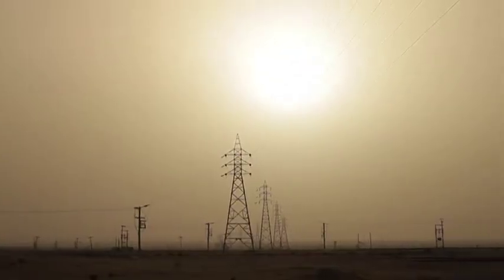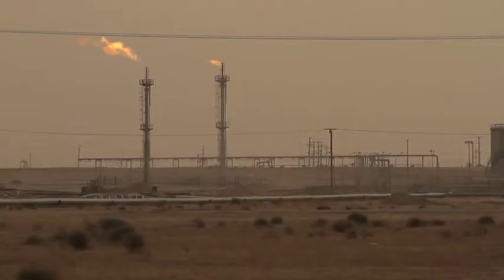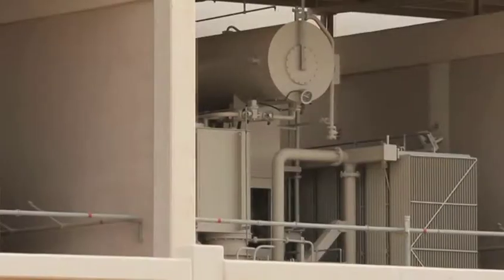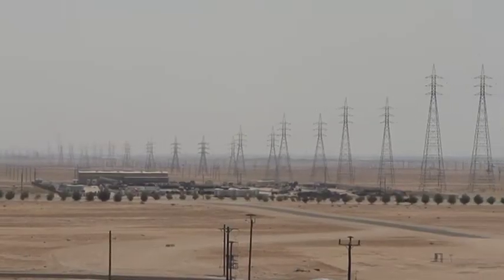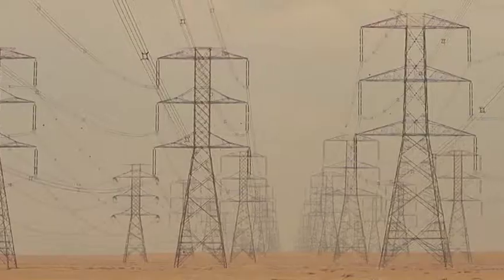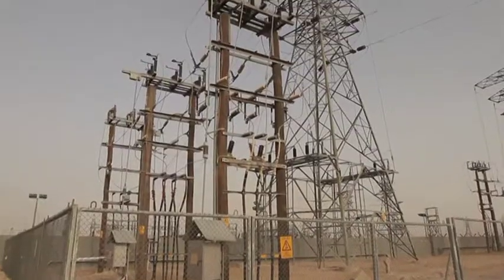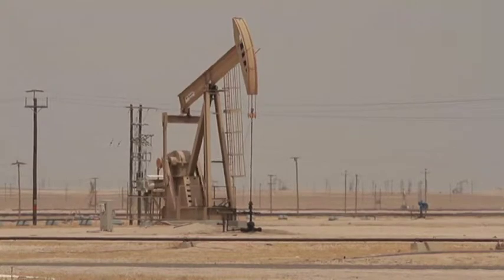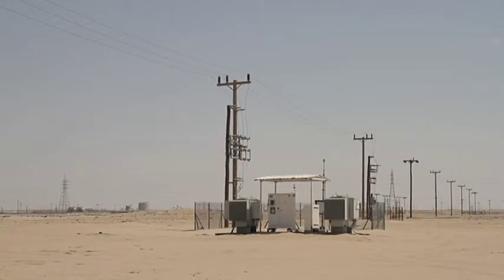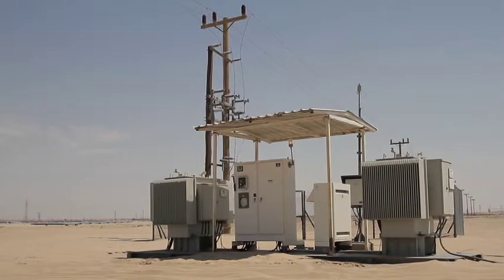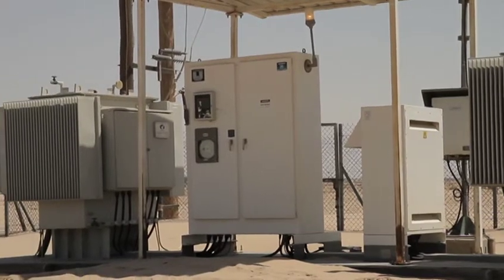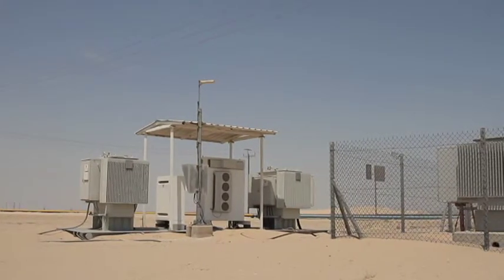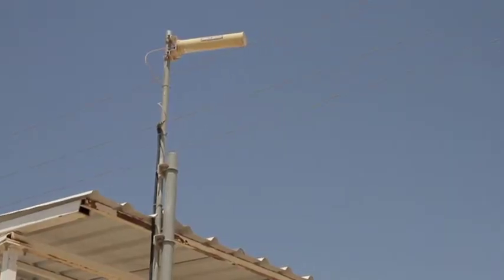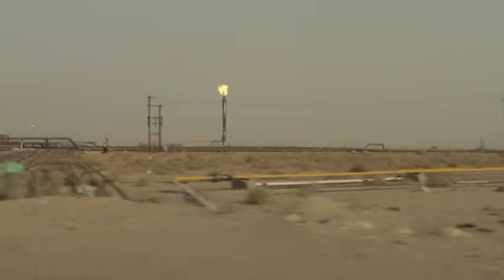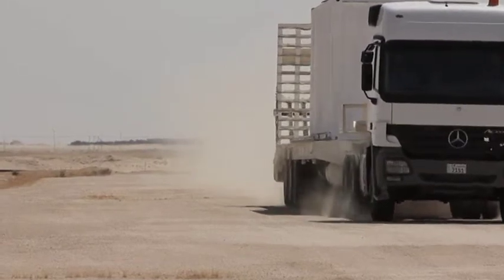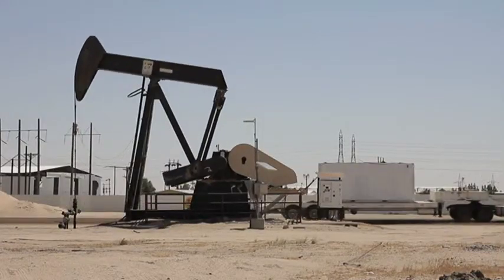The efficient exploitation of an electrically powered oil field requires optimizing the operation of its internal power distribution network. Medium voltage feeders in these networks are normally very long. Therefore, they are subject to significant voltage drops and undesirable losses, especially so when they are operated at or near full load conditions. Besides, modern electro-submersible pumps equipped with variable speed drives introduce harmonic disturbances which need to be mitigated in order to avoid damages to delicate control and protection electronic systems. All these problems can be solved reliably and cost-efficiently by installing reactive compensation systems and harmonic filters at selected nodes in the distribution network.